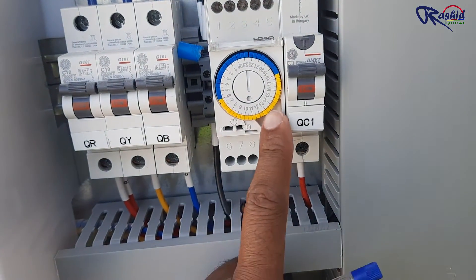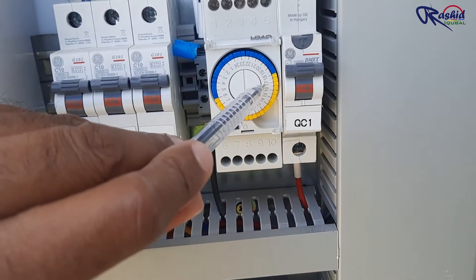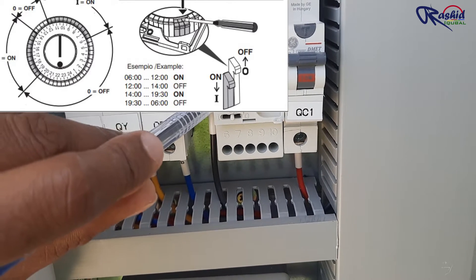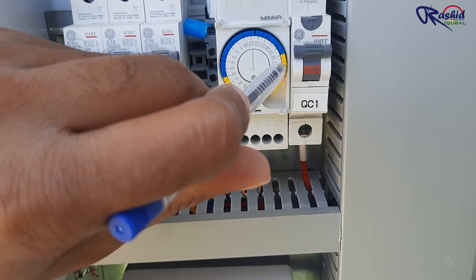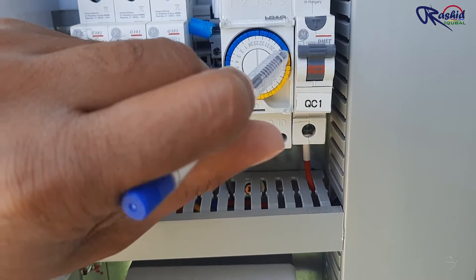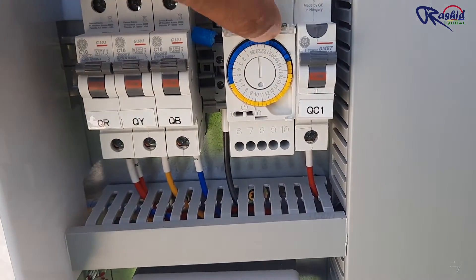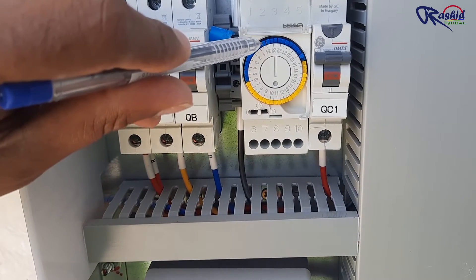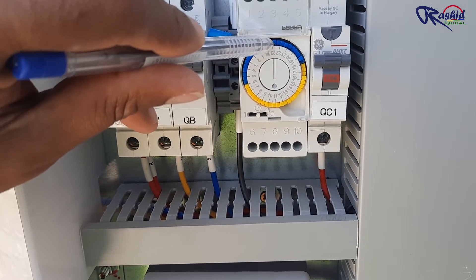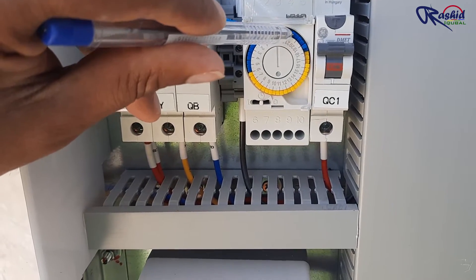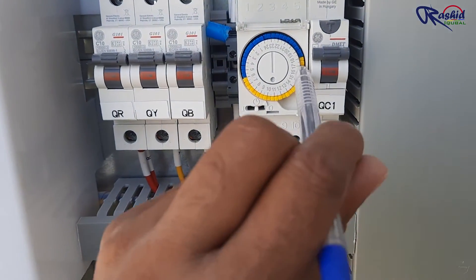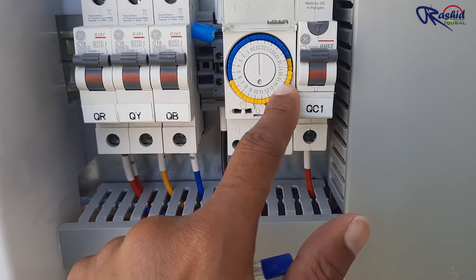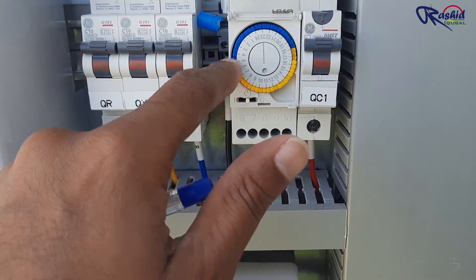Now I am going to set up the switch on and off time for the street light. We can push or pull up these pins — if you pull a pin up the timer is off, and if you push it down the timer is on. I want to turn on the light at 5 pm until 6 am in the morning, so I need to push the pins from 17 to 6. When the feeder pillar is energized, the timer's round shape starts rotating like a clock. Once the pushed pin reaches the arrow, the timer will activate and give a signal to the MCB to energize the outgoing circuit.